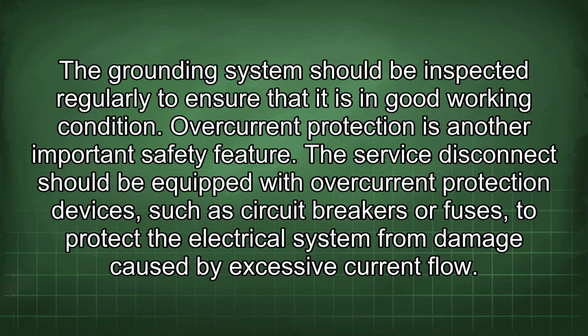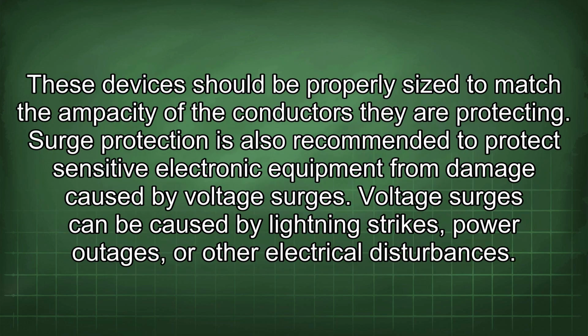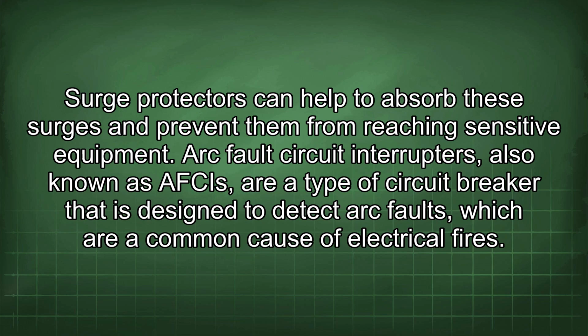Overcurrent protection is another important safety feature. The service disconnect should be equipped with overcurrent protection devices, such as circuit breakers or fuses, to protect the electrical system from damage caused by excessive current flow. These devices should be properly sized to match the ampacity of the conductors they are protecting. Surge protection is also recommended to protect sensitive electronic equipment from damage caused by voltage surges. Voltage surges can be caused by lightning strikes, power outages, or other electrical disturbances. Surge protectors can help to absorb these surges and prevent them from reaching sensitive equipment.